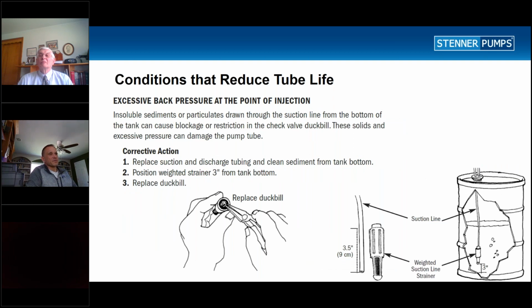Here we go through the instructions on how to replace the duckbill, and of course putting the weighted suction strainer 3 inches from the bottom of the tank. Now, when you're changing solution or servicing the pump, I always recommend taking that weighted suction strainer out of the solution tank and making sure that nothing's crusting up on the bottom of it. Oftentimes what I'll do is take an old toothbrush and, with the weighted suction strainer underwater, just clean it off in case chlorine or anything else has gathered on the bottom and plugged up the strainer.